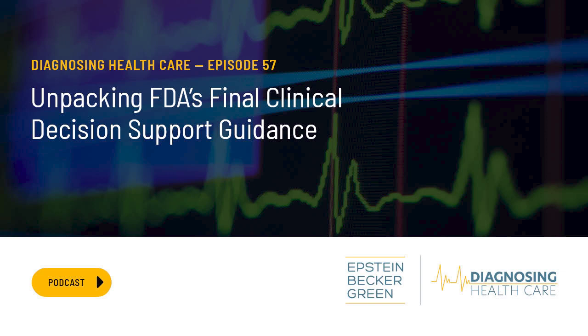I'd say there are two things that FDA tried to accomplish in the 2022 final. The first is to impose what I would call quality requirements on the data that are used to underpin the recommendation that's made. And so there's language in the final draft about it has to be the equivalent of peer-reviewed literature. And that's a huge problem for anyone, again, who wants to use machine learning, because machine learning typically wouldn't be done on a peer-reviewed set of data.